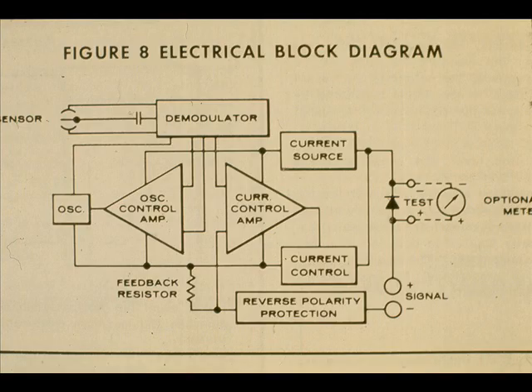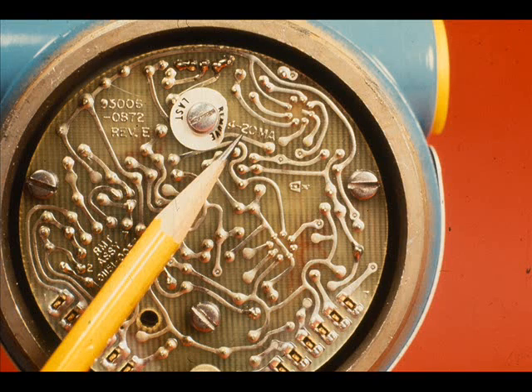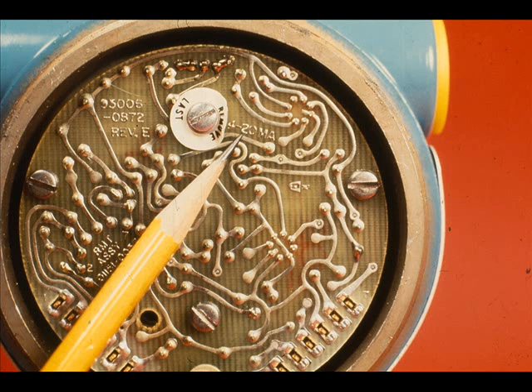This is an electrical block diagram of the circuit. The transmitter output can be either 4 to 20 or 10 to 50 milliamperes DC, depending on which amplifier circuit board is used. This is a 4 to 20 milliamp amplifier circuit board.